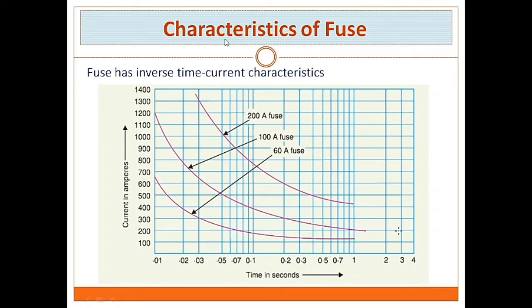Next are the characteristics of a fuse. The time required to blow out the fuse depends on the magnitude of the excessive current. The greater the current, the smaller is the time taken by the fuse to blow out — so it has inverse characteristics. If current is large, time is small; if current is small, time is large. Because a large current can cause significant damage in the system, we have to clear the faulty section as early as possible. That is why a fuse has inverse time characteristics.